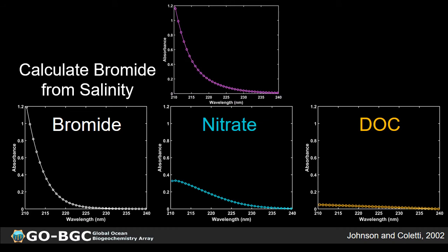This is kind of the Three Stooges problem. When you try to fit all three spectra at once, it's like the Three Stooges trying to go through the door at once; you don't get the best results. So how do you get around this Three Stooges problem? Well, we take advantage of the fact that you can actually calculate the concentration of bromide from salinity. Since absorbance is related to concentration, if you know salinity, then you should be able to calculate the absorbance spectrum for bromide and subtract it out from the overall measured absorbance spectrum. That will leave you with only trying to differentiate nitrate and DOC, which would substantially simplify the situation. But you need a little bit more information than just salinity to do this.